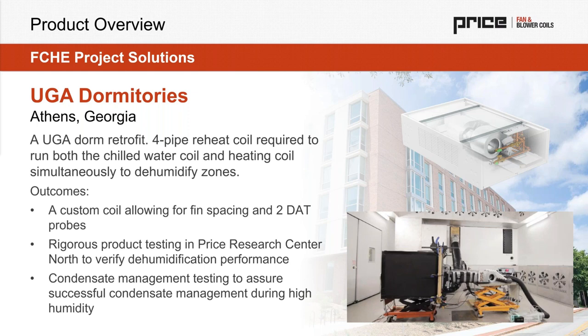And generally, most manufacturers, to save costs, would integrate the cooling and heating coil into one fin pack. It allows it to move through production a little bit more easily, and it's easier to manufacture. Spacing those coils out is a harder task, but one in this case that provided a lot of value to the project in order to allow for that dehumidification to take place. And once again, this was something that required rigorous testing in our lab up in Winnipeg, in our psych chamber, which can provide about 10% to 100% relative humidity, 35 to about 110 degrees Fahrenheit within the space, and supply water temperatures from 30 to 210 degrees Fahrenheit as well.